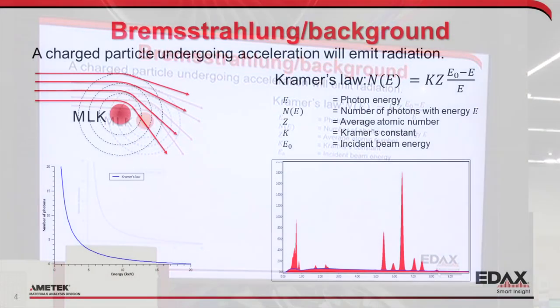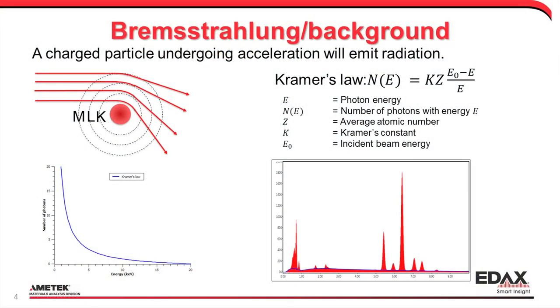The emitted radiation from this can be described by Kramers' law. Basically, the number of photons depends on the average atomic number of the sample — the larger the core, the more positive charge, the more we bend the incoming electrons — plus Kramers' constant and the incident beam energy. So it changes with the acceleration voltage of the microscope as well.